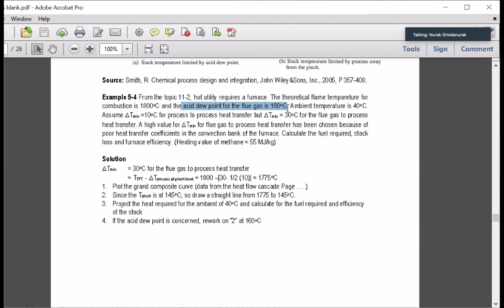I just want to show you - if your fuel contains some sulfur, you cannot use or answer based on the blue line. You have to answer on the red line, because the red line is 160 degrees Celsius. It's difficult to draw differently, so I leave the red dot over here. The red line represents the flame temperature passing to the dew point. The blue line, slightly below, represents our own calculation.